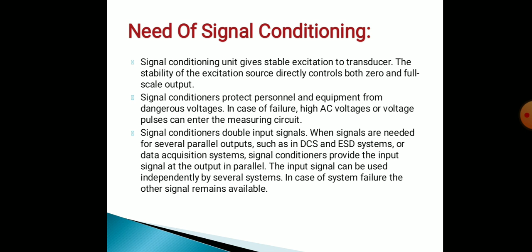Signal conditioners double the input signal when signals are needed for several parallel outputs, such as in DCS or ESD systems or data acquisition systems. Signal conditioners provide the input signal at the output in parallel. The input signal can be used independently by several systems. In case of system failure, the other signal remains available. By using signal conditioners, we can provide a signal which is increased in value. We can give amplification, like doubling the input signal, and we can use it independently, so that if a system fails, other signals remain available.